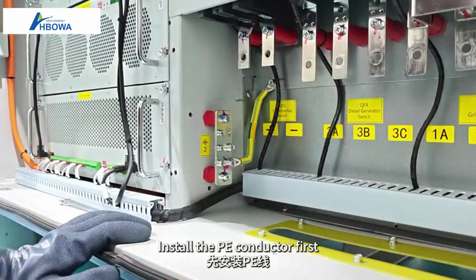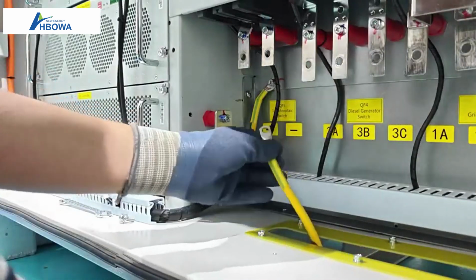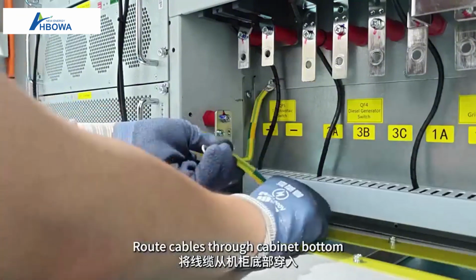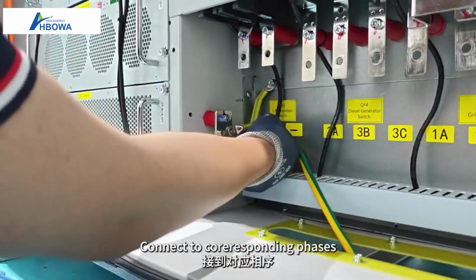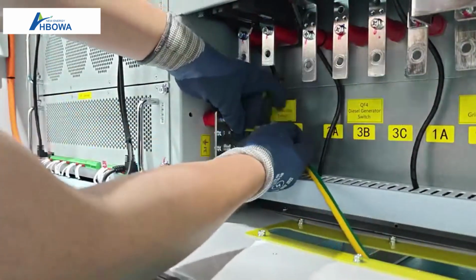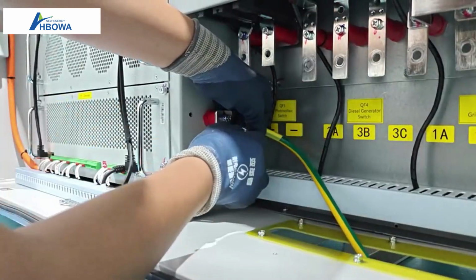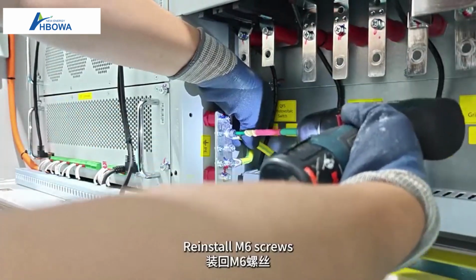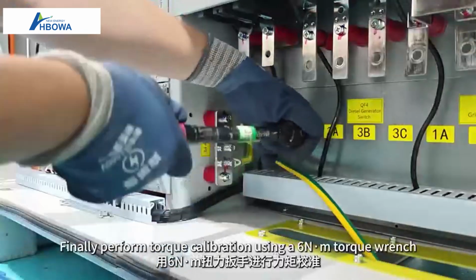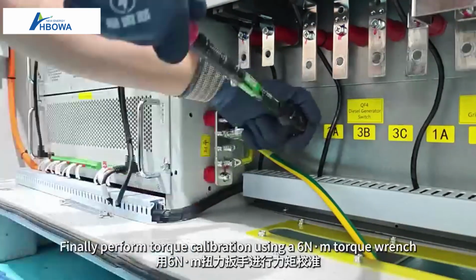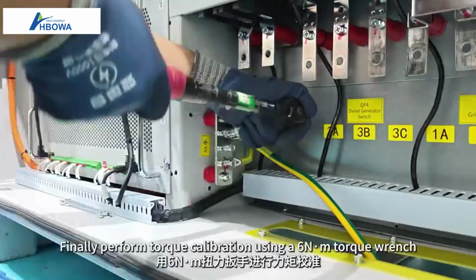Install the PE conductor first. Route cables through cabinet bottom. Connect to corresponding phases. Reinstall M6 screws. Finally, perform torque calibration using a 6 Nm torque wrench.